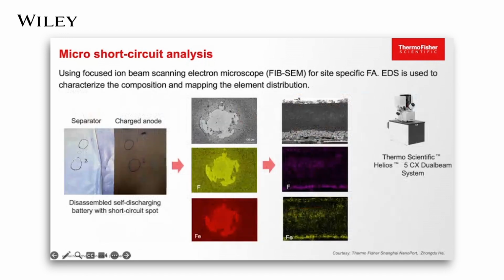I would like to share another use case for micro short circuit analysis with dual beam for a lithium iron phosphate battery. This should be a high self-discharging battery after dismantling the battery in a fully charged state. We did find the suspicious site of short circuit on the fully charged golden anode electrode. Then we cut across the site on the separator with dual beam and found the pores are blocked. The pores of the separator are blocked in a large area.